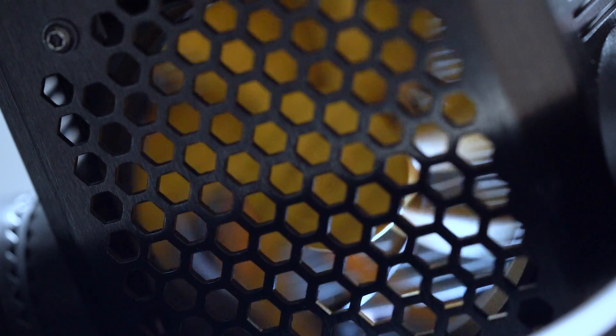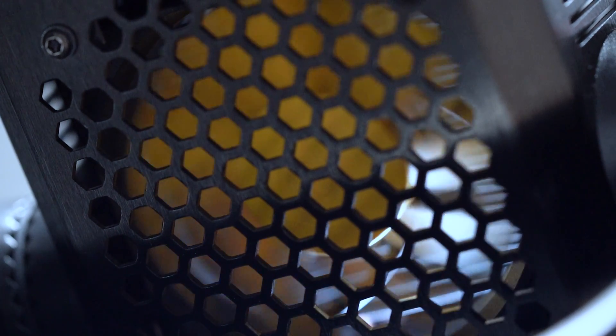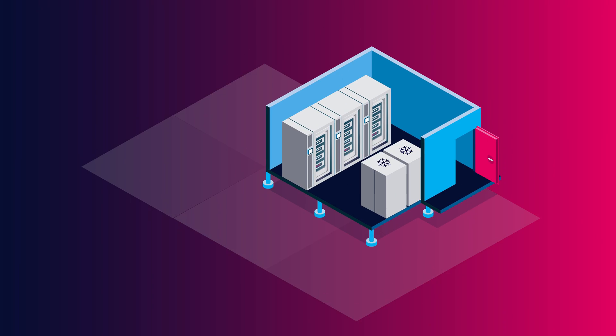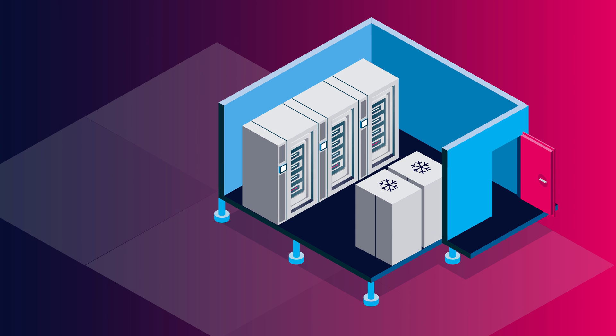As with any data center, it was important to keep the server room cool since the servers would automatically shut down if a certain temperature was exceeded. To keep it cool, it was equipped with standard but very ancient air conditioning units. It was designed redundantly with a main and backup AC unit. The AC worked by pulling air under the floor to cool it before bringing the cool air up in front of the server racks. But because of the age of the AC units, there was a problem — we couldn't directly monitor them because there was no network interface.